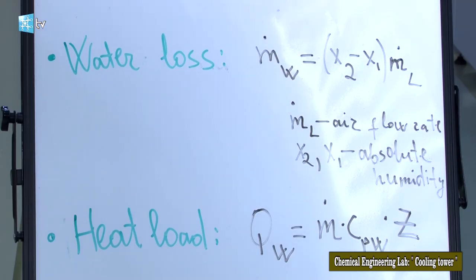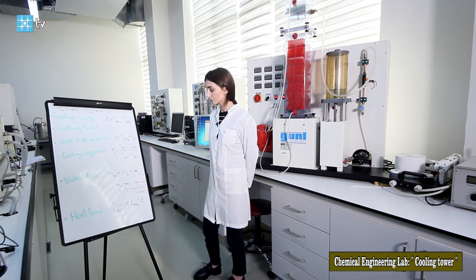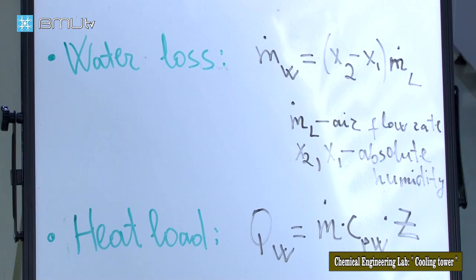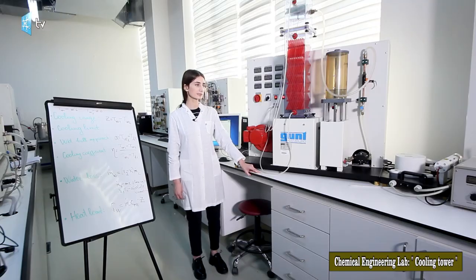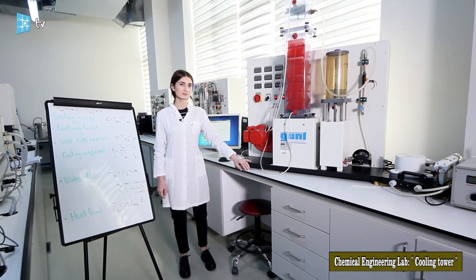Water loss can be calculated as the difference in absolute humidity at the air inlet and outlet multiplied by the air flow rate. Heat load is the product of the water flow rate times the specific heat of water times the cooling range of the process. In this experiment, we demonstrated the influence of air flow rate, water flow rate, and cooling water temperature on cooling performance. The findings revealed that volumetric air flow rate and cooling water temperature enhance cooling performance, while increasing water flow rate decreases it. That's it for today's lesson — see you next lesson.